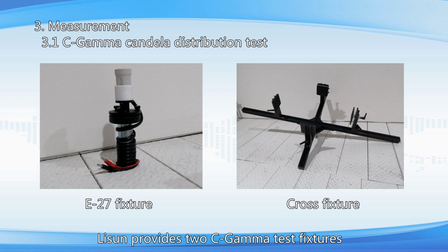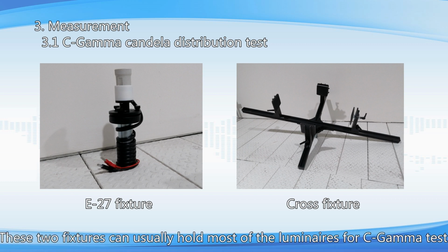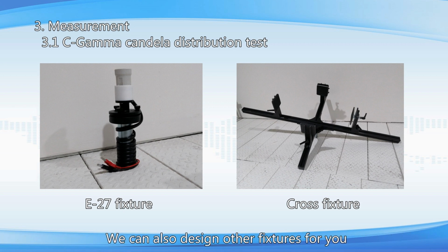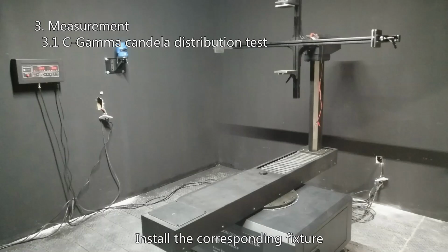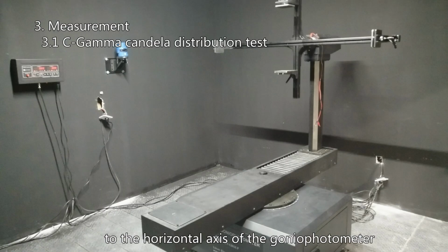Lisun provides two C-Gamma test fixtures: E27 bulb fixture and large cross fixture. These two fixtures can usually hold most of the luminaires for C gamma test. We can also design other fixtures for you if you have special luminaires to test. Install the corresponding fixture to the horizontal axis of the goniophotometer.